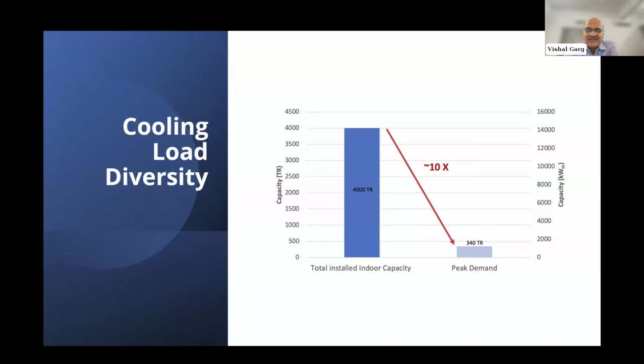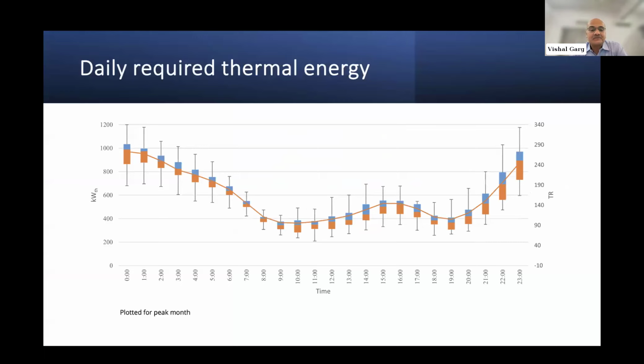Not all the air conditioners are running in the night. So if somebody has 4 bedrooms, maybe 1 bedroom is being used, and dining, drawing, these rooms are not being used. So it can easily come down. Not everybody uses air conditioning. Then there would be some people traveling, but then there would be some guests. So it kind of balances out. And the split ACs will not have 100% duty cycle. They will switch on and off. So here, if we are just doing centralized air conditioning, I mean, doing a chilled water system, then the installed capacity can come down by 10x.